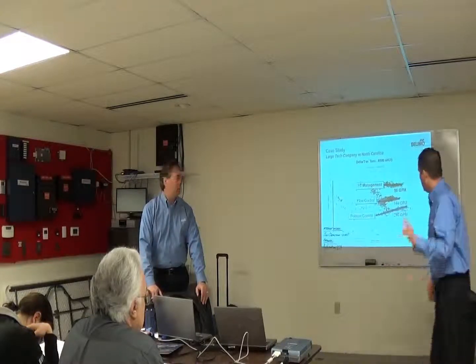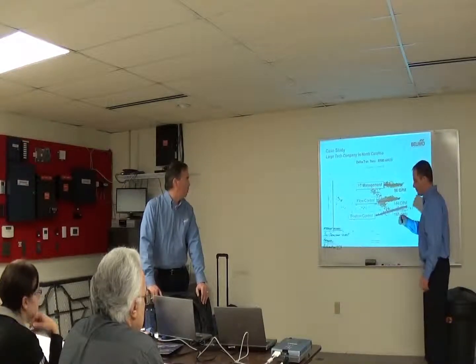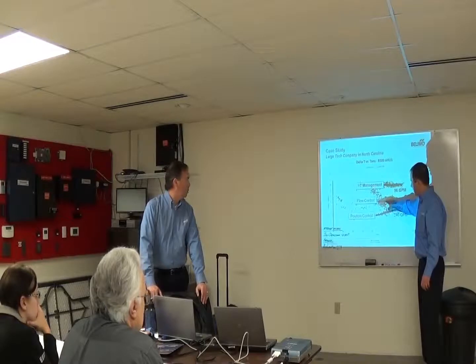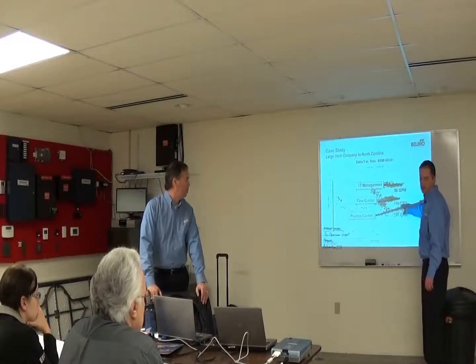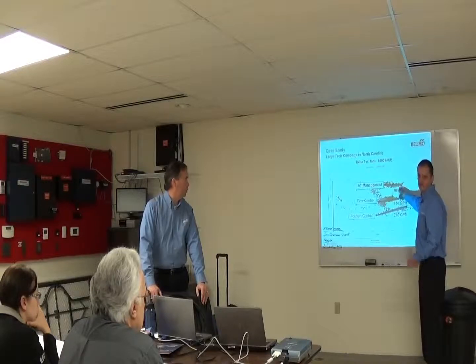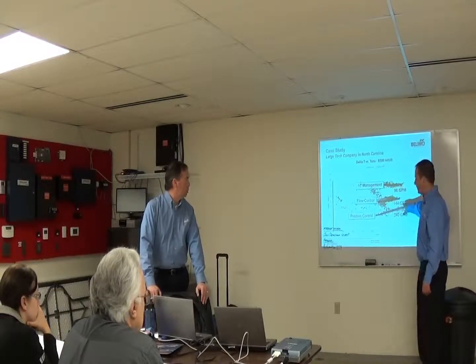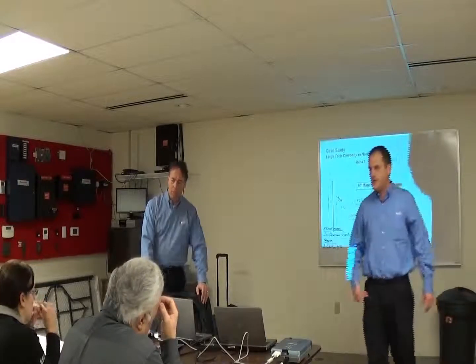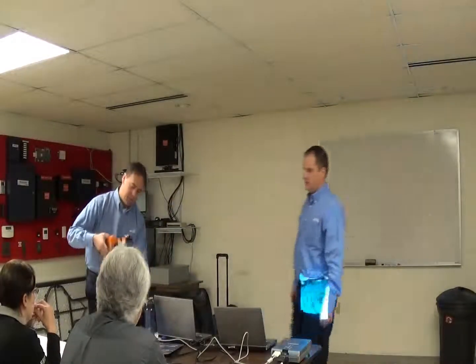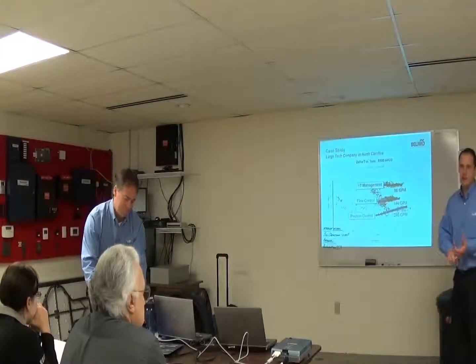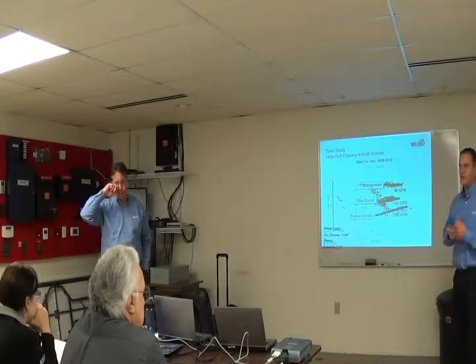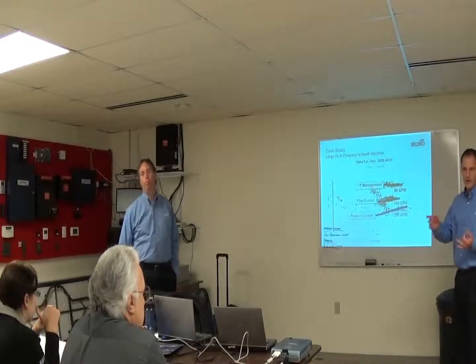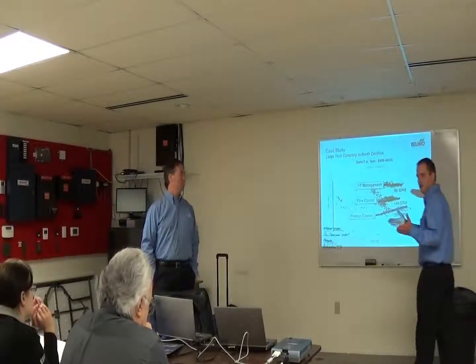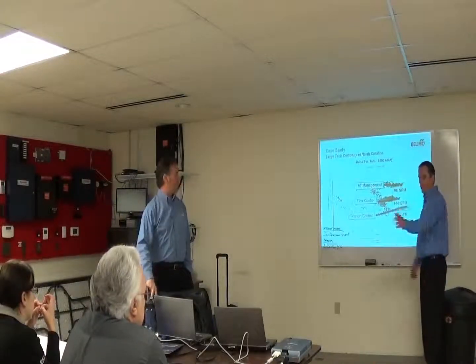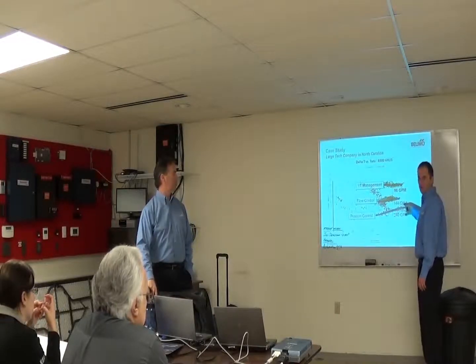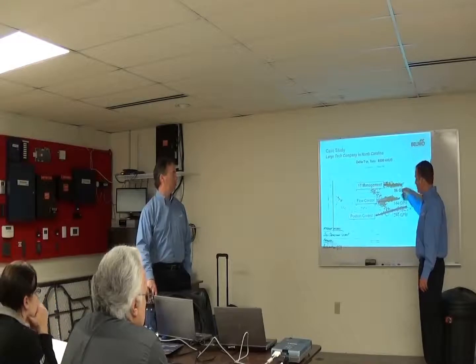Electronic pressure independent. But just real quick, before I forget this, we talk about this energy valve and all this, but this is pressure dependent to pressure independent, okay? So that's the savings between the two technologies. And this is nice, this is Delta T Manager, but we've got another product called the EPIV, which is basically the same thing without these sensors. It doesn't have BACnet, doesn't have a web server, but it has a flow meter. We'll give you the feedback, so you can hook that feedback right up to your control system. So a 2 to 10 out and a 2 to 10 back. That 2 to 10 is scaled up to flow range. So with that product, or with our mechanical pressure independent product, this is the savings they would have got. This is just icing on the cake.